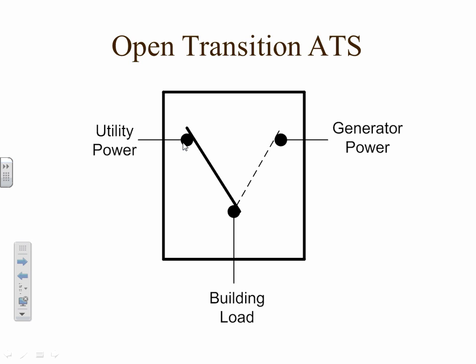It's going to take between 7 and 10 times rated running current to get that motor running, right? And more importantly, if you look at the power factor of that motor, it's going to take a lot of kW, or real power, horsepower, to do it. So even with the utility trying to start hospital chillers, residential air conditioning, RTUs, and low-rise complex, all at the same time, it may or may not do it. So the utility might go right back down again.